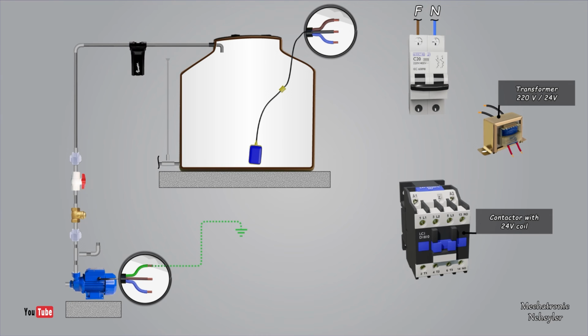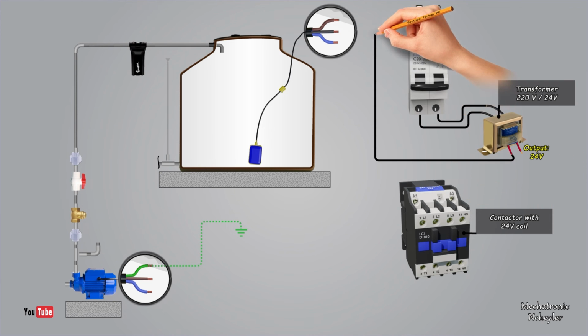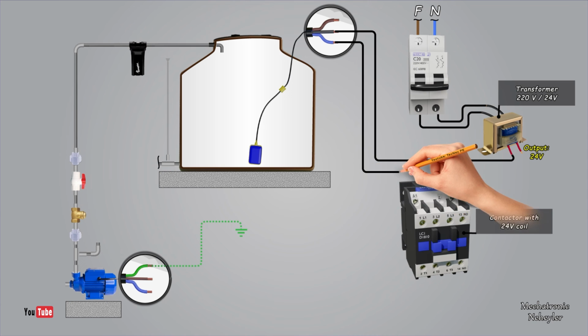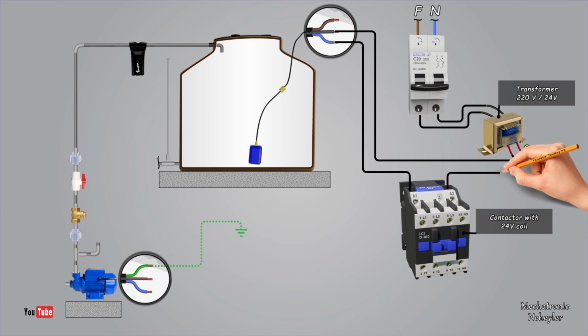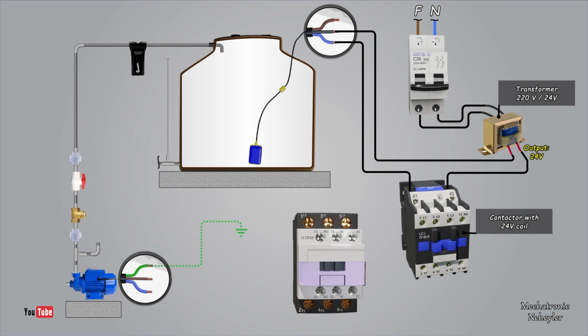For wiring the floats, which is the control part. First, it must be connected to the transformer and thus obtain a voltage of 24 volts at its output. From one of the output wires of the transformer, it is connected and led to the common black wire of the float. From the light blue cable of the float, it is connected and taken to terminal A1 of the contactor, and from terminal A2 of the contactor it is connected and taken to the remaining cable of the transformer. For this circuit, thin wire is usually used, enough to withstand the current of the coil and the voltage of 24 volts. There are other contactor models, in which the arrangement of terminals is different, as shown, but it must always be taken into account that the cables that include the float must be connected to coil A1 and A2.